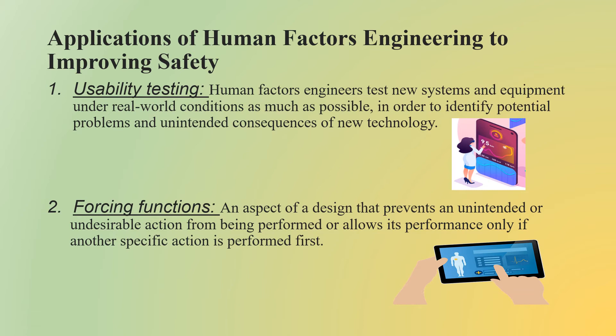Another tool that the human factors engineering approach uses is forcing functions. An aspect of a design that prevents an unintended or undesirable action from being performed, or allows its performance only if another specific action is performed first. Forcing functions are used as a tool to improve patient safety. They are built into technology as hard stops — an activity that forces the user to take action. If your system forces you to document a time out before you can document further in the process, then it is called a forcing function.